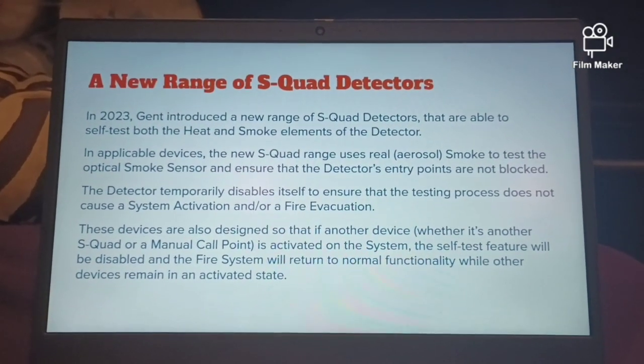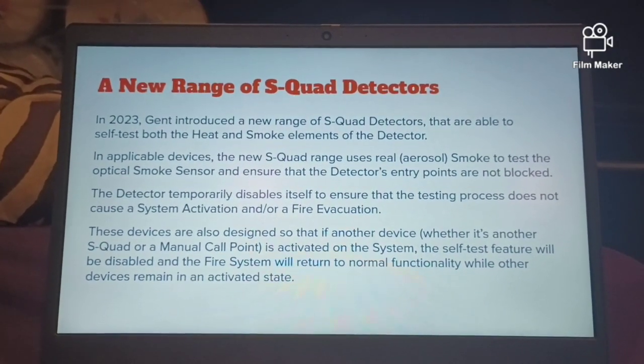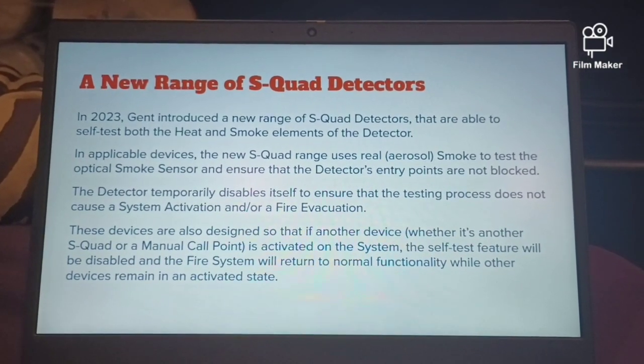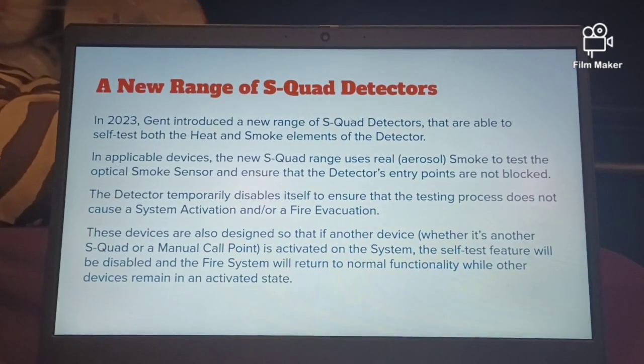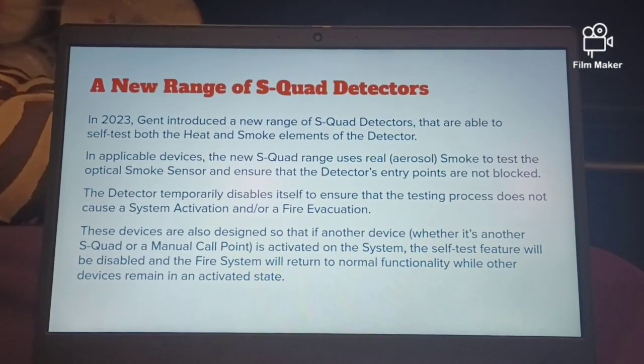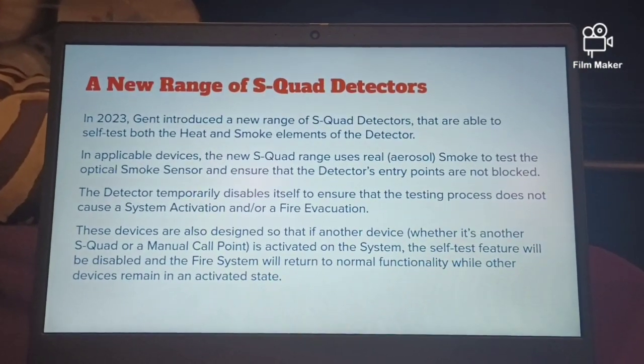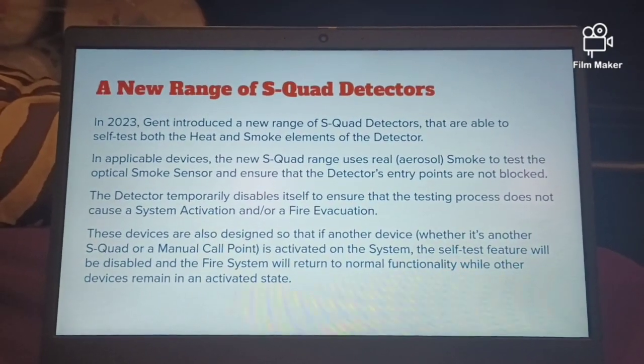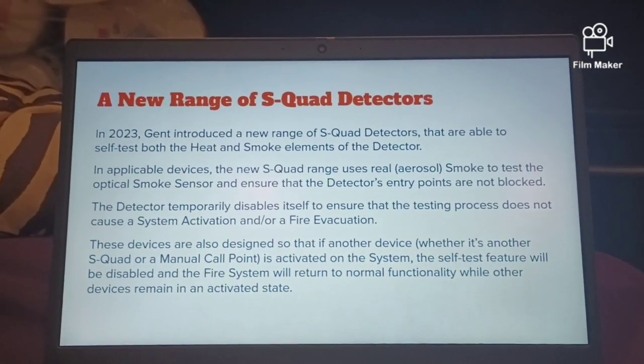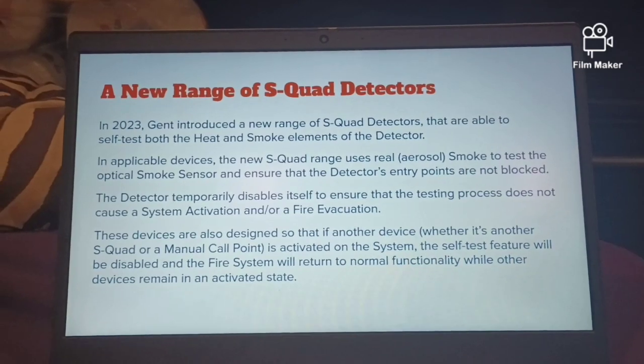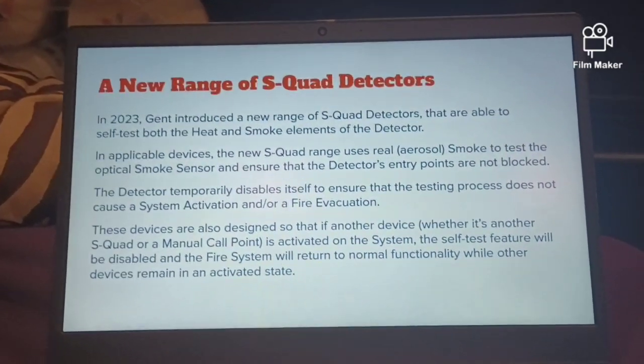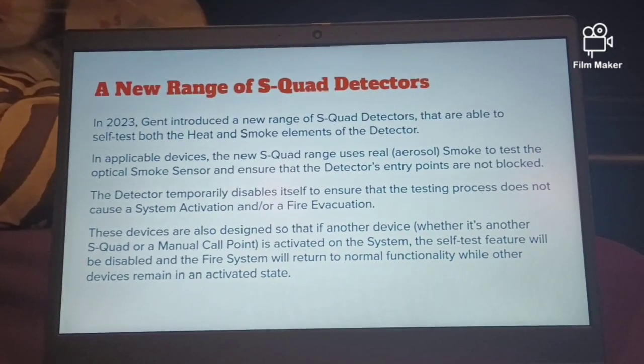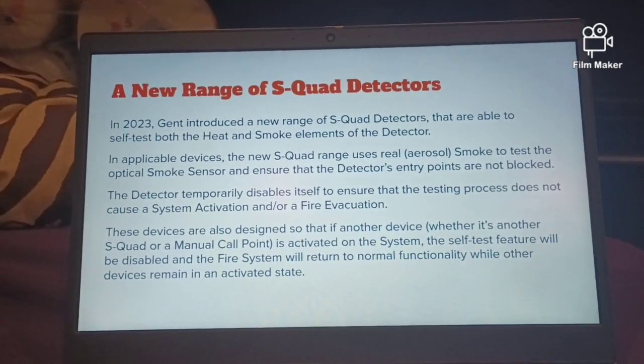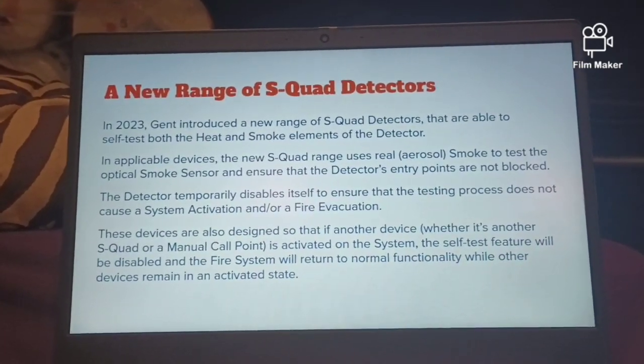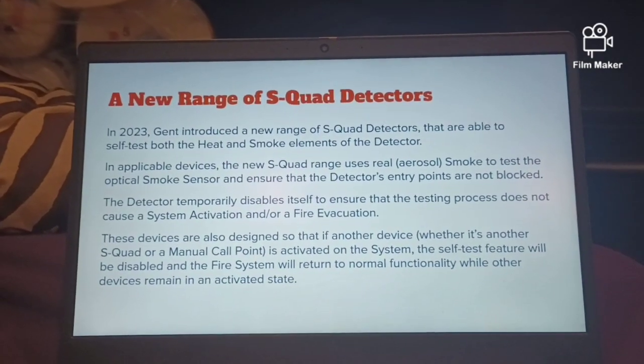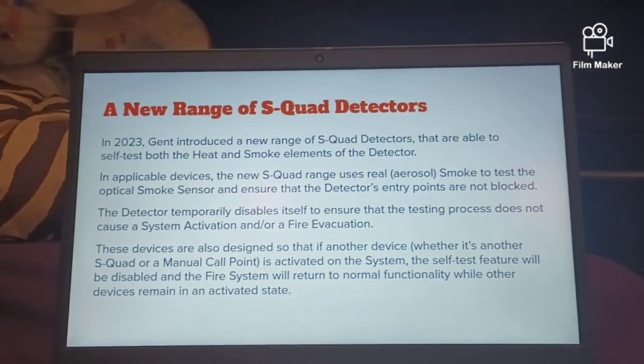The detector temporarily disables itself to ensure the testing process does not cause a system activation and or a fire evacuation. These devices are also designed so that if another device, whether it's another S-Quad or a manual call point, is activated on the system, the self-test feature will be disabled and the fire system will return to normal functionality while other devices remain in an activated state.